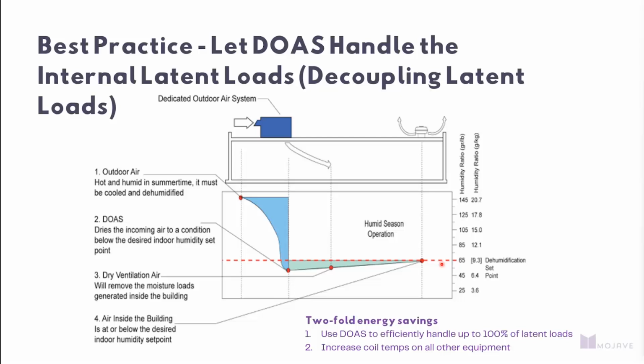And you'll actually wind up, if you're discharging here, missing your zone condition and floating above it and have a space that's out of zone target, really, at the end of the day. So best practice, I would encourage everyone to look at discharging a few degrees under your zone target condition to allow for natural infiltration and, frankly, being able to hit your zone condition.